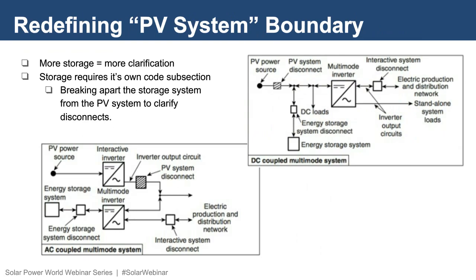The 2017 code cycle introduced a more explicit PV system boundary which 690 would encompass. The PV system boundary is now considered the point where the PV system equipment couples with other sources on the same electrical system. As such, the PV system boundary varies depending on system type. Further, energy storage systems are no longer covered in NEC 690 and have their own place in Article 706 of Chapter 7.